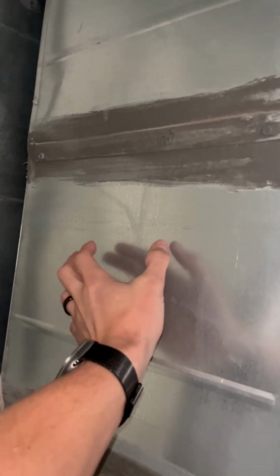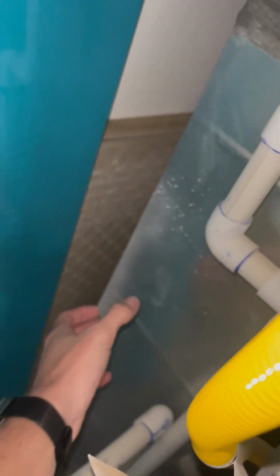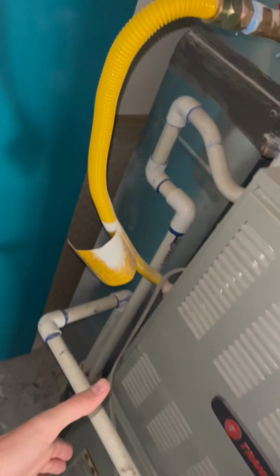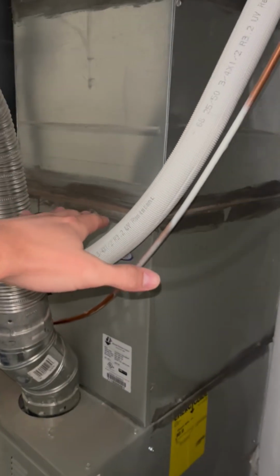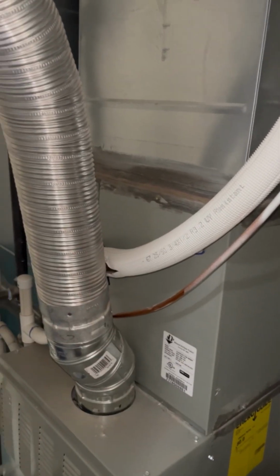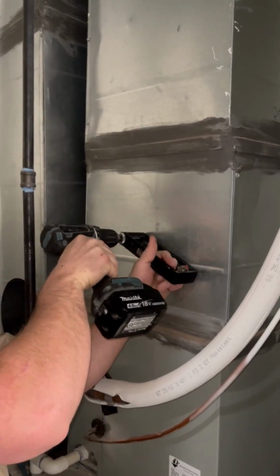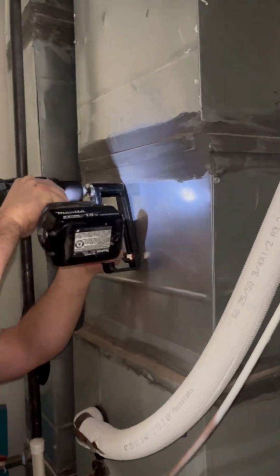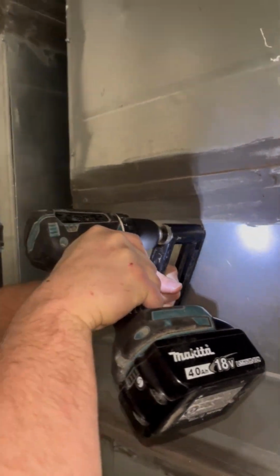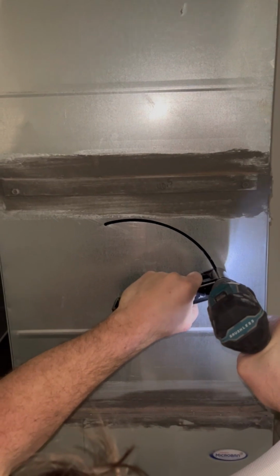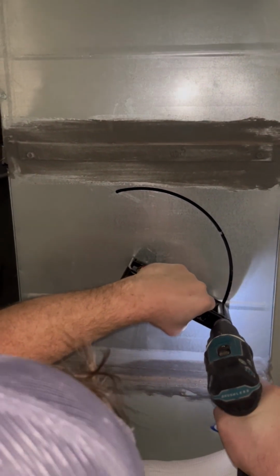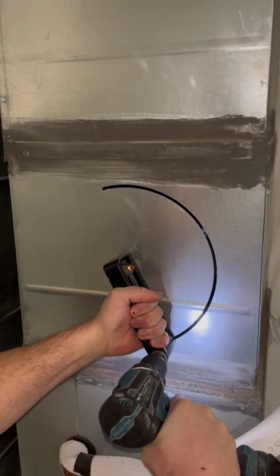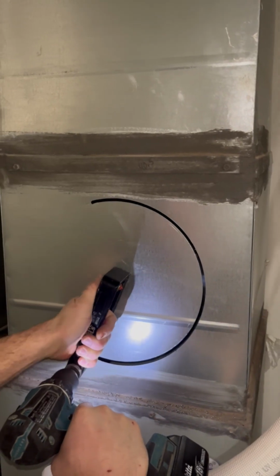To inject the sealant, we cut an access hole on the supply side and on the return side, where we can then insert foam plugs to make sure none of the glue gets on the actual coils. Using an attachment on our drill, we can cut a circular access hole in the supply opening and again in the return. We have this portion of the video sped up about 2.5x, but it's still pretty quick even in regular time.